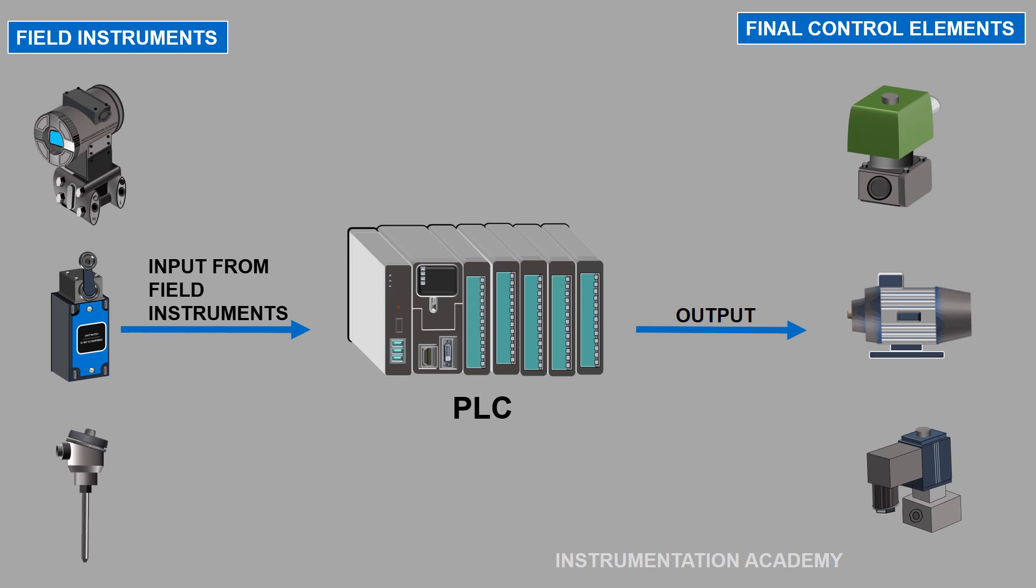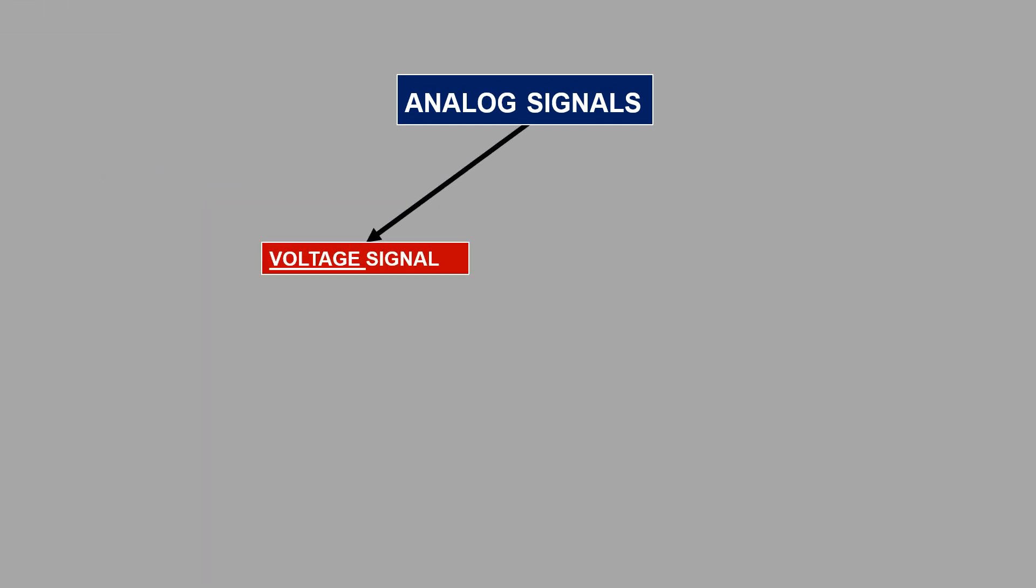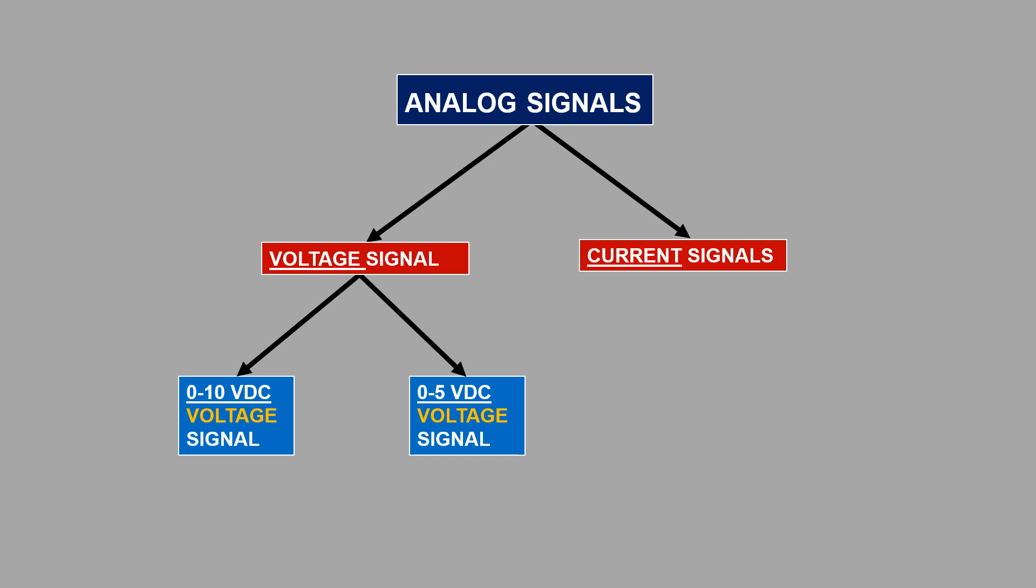The input or output of a controller like PLC can be an analog or a digital signal. The analog signal can be transmitted as either a voltage signal or current signal. Usually, analog voltage signal can be 0 to 10 volt or sometimes 0 to 5 volt, and analog current signal can be typically 4 to 20 mA.